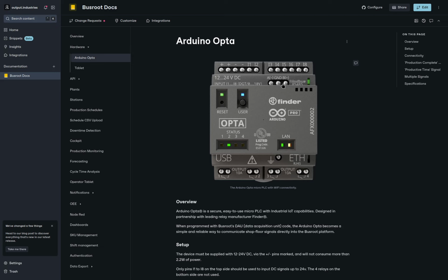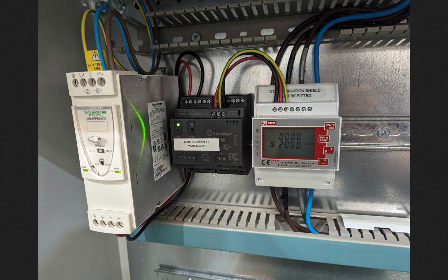so that during the installation process, we'll get told that input 1 is the andon light for machine 1, input 2 is the production count for machine 1, input 3 can then be used for maybe a second machine, and so on, all done in the cloud and configured remotely. So it makes the installation process very, very simple for us by using a device like this. And this device also connects through to energy monitoring. So it really is a universal device for us.